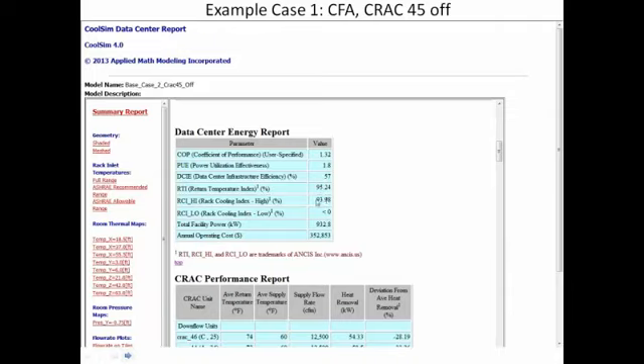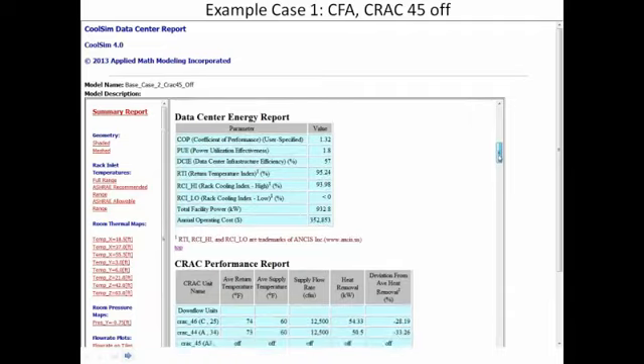We are running into hotspots, and we're running into hotspots despite the fact that our RCI low is less than 0, which means we're way too cold. So a typical case, I think, that we see a lot: CRAC units running too cold at delivery temperature, which means terrible efficiency. The energy efficiency here is really quite awful. You see a PUE of 1.8, which means that it's almost taking as much energy to drive the cooling system as it is to drive the IT load. So you're paying twice for the electricity going to your servers, and it's because of poor airflow in the room.